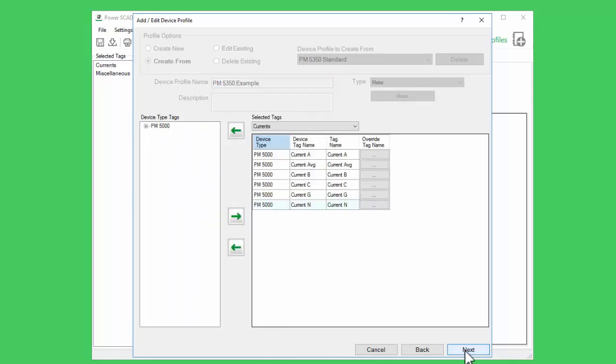Inside the alarm server, a PC-based alarm tag will take a value from a variable tag, compare it to the alarm tag's configuration, and set the alarm state accordingly. An onboard alarm, in contrast, is calculated inside the device and is written to the device's internal event log. In this case, the alarm server doesn't make any calculations on its own. Instead, the I/O server reads the device's event log. If there are any relevant alarms, the driver writes the alarm states and times to the alarm server directly.